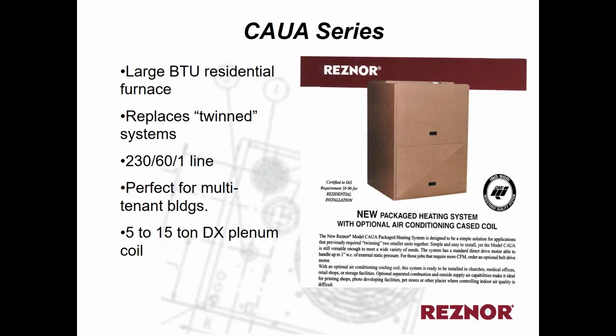The CAUA here is an indirect fired, large BTU input, almost residential type furnace. We make these units from 150,000 BTU up to 400,000 BTU. What this type of product eliminates is for the contractor to have to twin two residential furnaces together in a commercial application. This furnace starts out at 150,000 BTU, which is typically where residential product stops, and we make it up to 400,000.